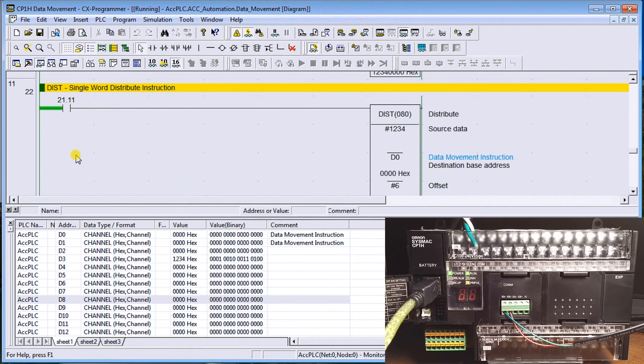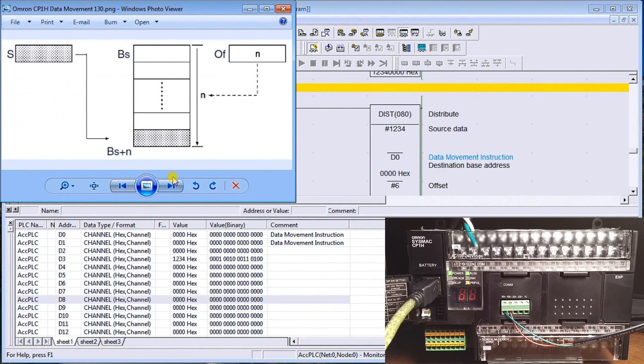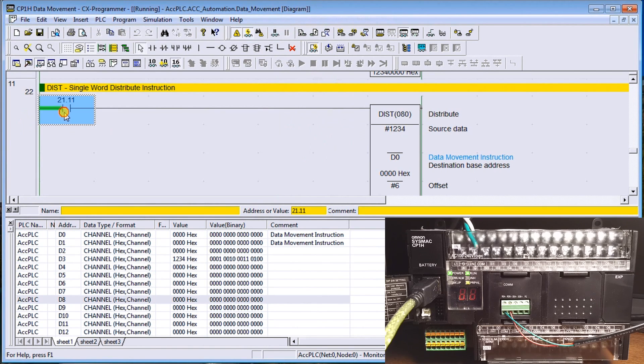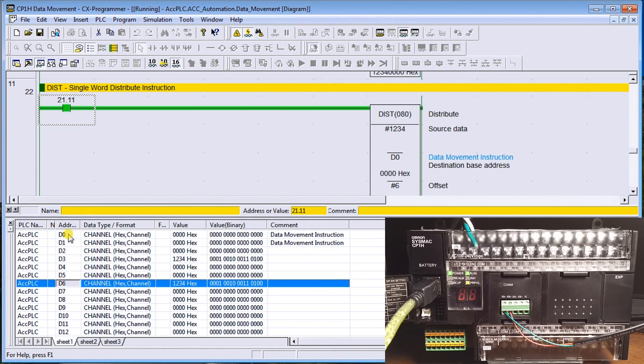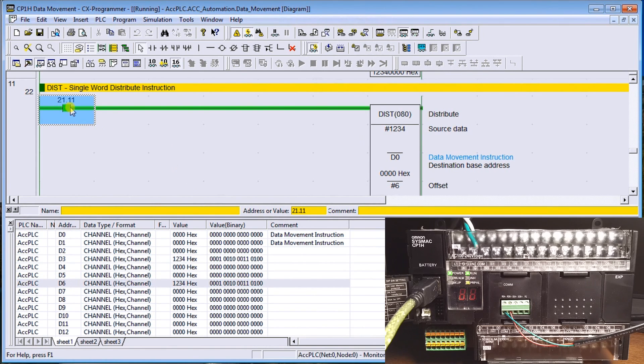Next is Single Word Distribute. It stores data from the source into a destination with an offset. The value 1234 is stored into destination D0 with an offset of six, meaning it should appear in data memory six. Turning it on, sure enough data memory zero plus offset six gives us data memory six containing 1234. The offset tells it exactly where to put the information.